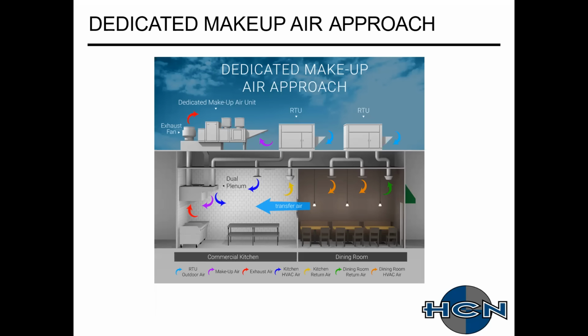And then that outside air that the RTU is sized for, because we're adding that extra load, it's not typically accounted for. So you're getting a kind of cycling effect of, hey, our system's not working, we're going to try to put in more exhaust, or bring in more makeup air. And usually the problem there is not that. It's usually, we can improve your exhaust hood by doing a couple of things here or there.